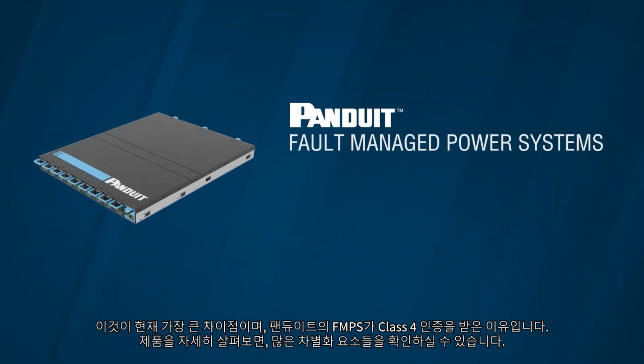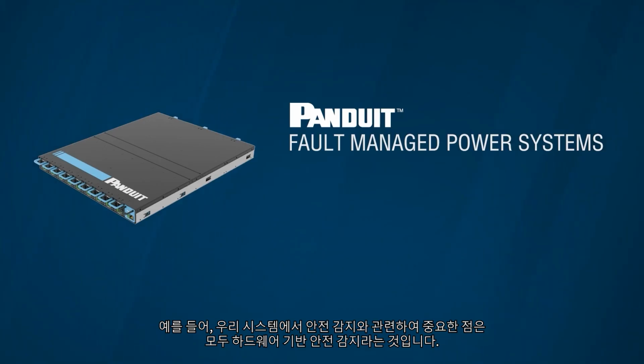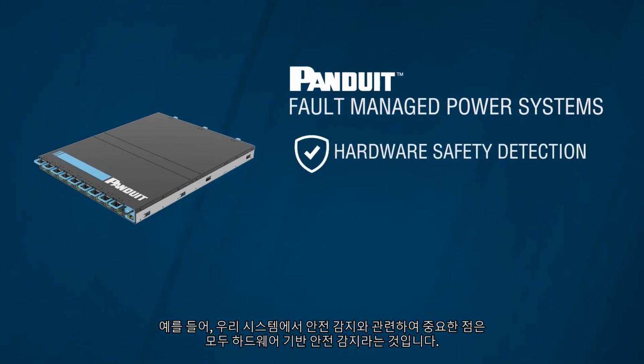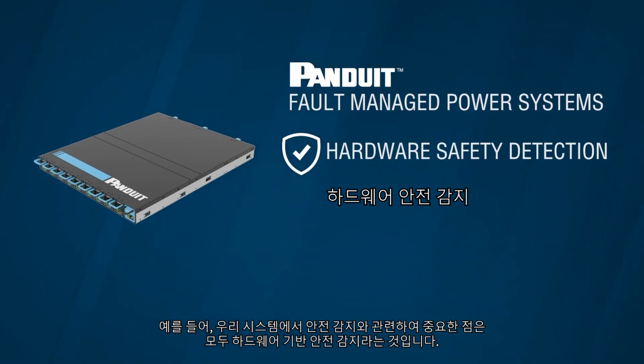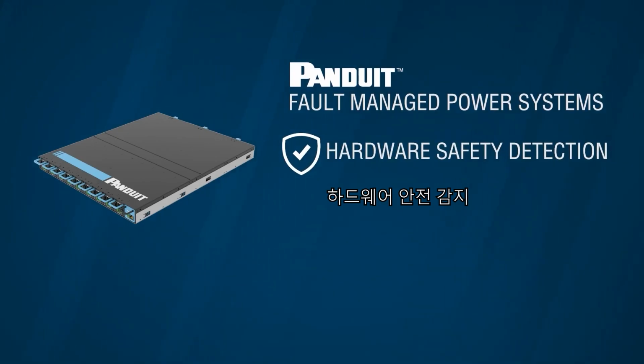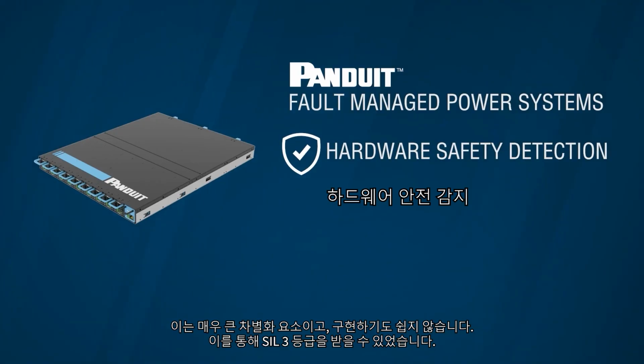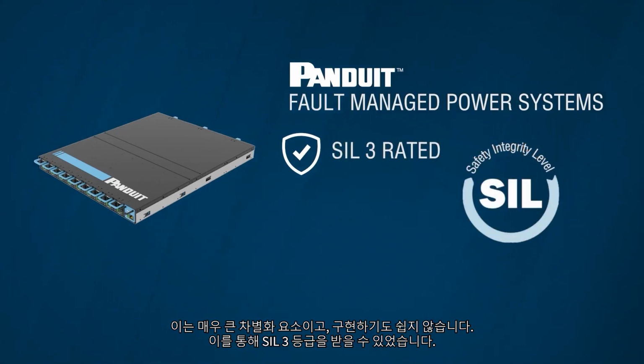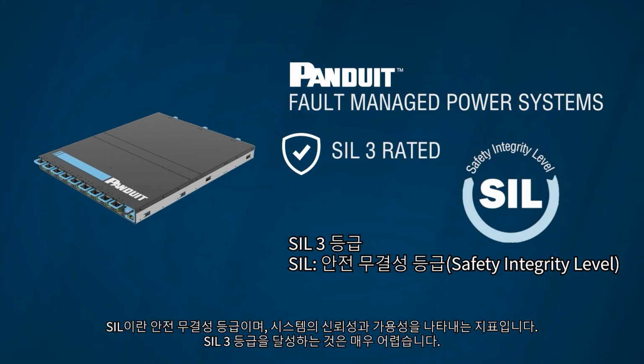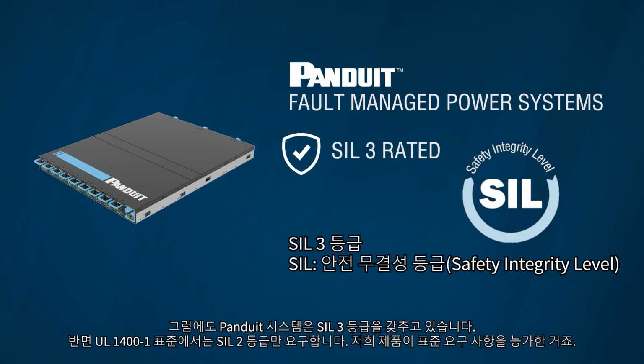Now, if you look at the details of the product, you'll find a lot of other differentiations. For instance, a big part of our system in terms of the safety detection is that it's all hardware-based safety detection. That's a really big differentiation. It's hard to do, and it allows us to be what's called SIL 3 rated. SIL is safety integrity level. That speaks to the reliability of the system and how many nines. Achieving SIL 3 is really difficult. So our Panduit system is SIL 3 rated. The UL 1400-1 standard only asks for SIL 2 to comply, so we supersede what the standard asks for.